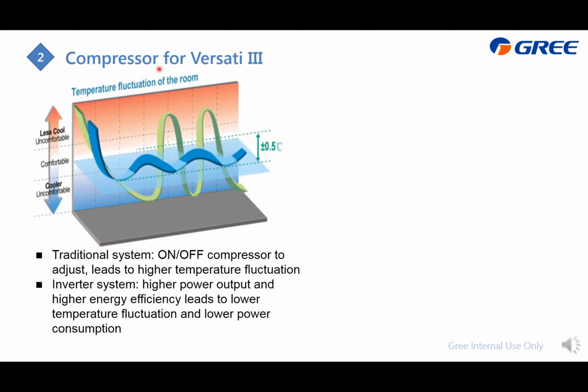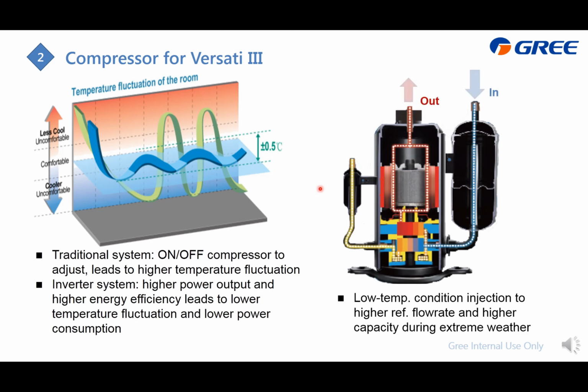The compressor of VERSATI is inverter. This is the comparison between the traditional on-off and the inverter system. This one is very basic, just to lower the indoor room temperature fluctuation. This is common sense, so we can skip. The most important thing for VERSATI3 is that it has another gas in. For a traditional compressor, it is just one in and one out, right? And for the VERSATI3, as we have the EVI, we need to inject from here another gas in, and it is something like a two-stage compressor, and this can help to raise the heating performance in low temperature.